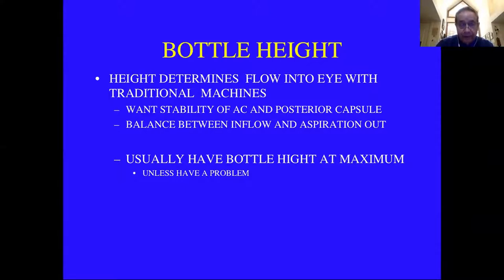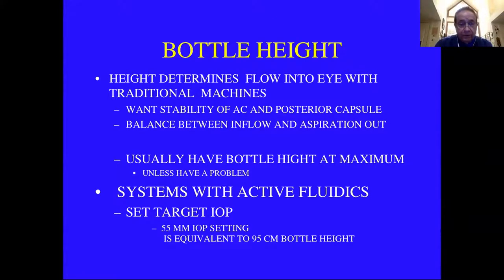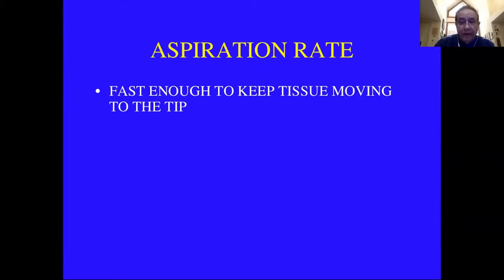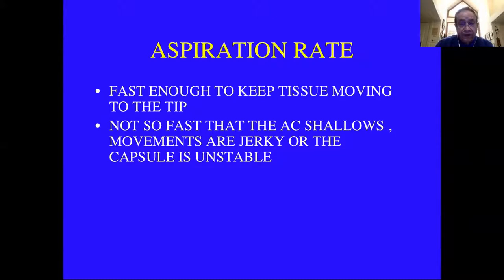If things are going reasonably normally, you want to have the bottle height at a maximum. If you have a problem — like grabbing iris or capsule — lower the bottle height and slow down your aspiration rate. With active fluidics systems, you set the target intraocular pressure. Setting it at 55 mmHg is approximately equivalent to 95 centimeters of bottle height, which is usually as high as the average gravity feed system goes. You want aspiration rate fast enough to keep tissue moving to the tip but not so fast that you have an unstable chamber. If movements are jerky or you're getting movement out of the posterior capsule, slow it down.